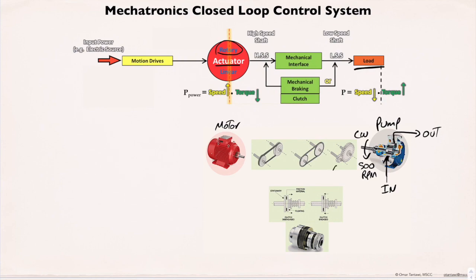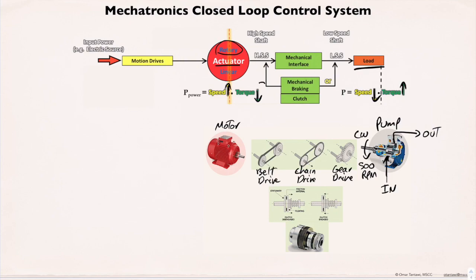In most applications, the motor shaft rotates at a higher speed with less torque than what the load requires. In this case, one of three mechanical drives must be used as a linkage — such as gear drive, chain drive, or belt drive — to match the motor speed and torque with the pump's rated speed and torque. Matching means decreasing the motor speed and increasing its torque by using different sizes of gears, sprockets, or pulleys.